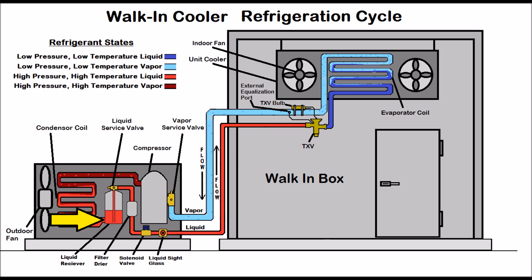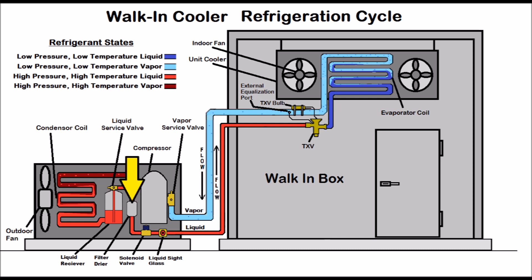The sub-cooled liquid gets sucked up through the liquid service valve on top of the receiver, then goes through the filter dryer. The filter dryer's job is to store any water vapor and contaminants, preventing water vapor from interacting with the refrigerant oil. If water vapor and refrigerant oil mix, it turns into alcohol and acids. So the sub-cooled liquid refrigerant heads through the filter dryer and then through the solenoid valve.